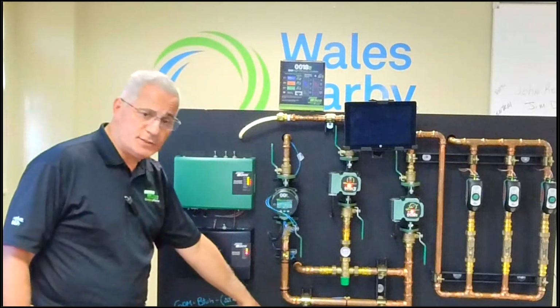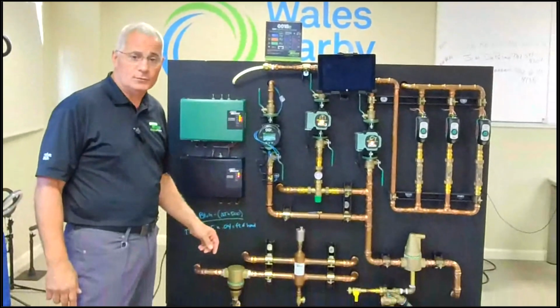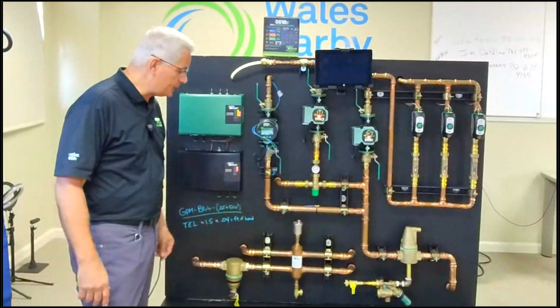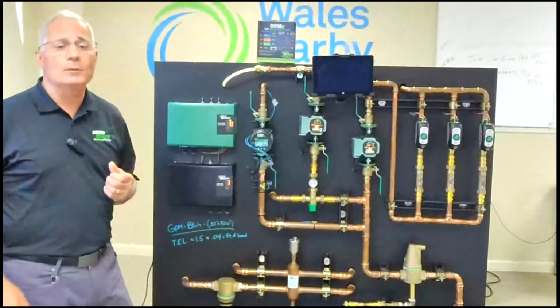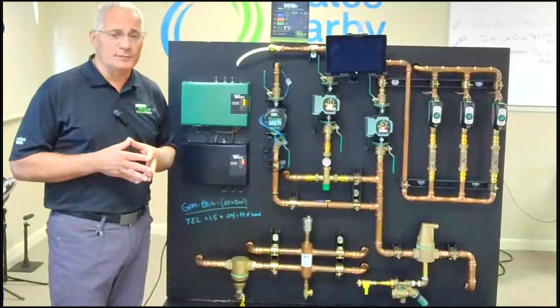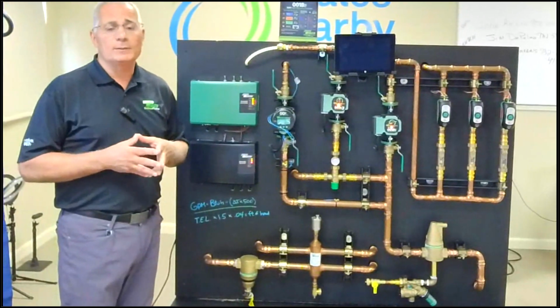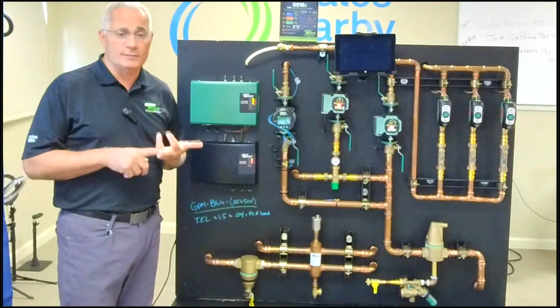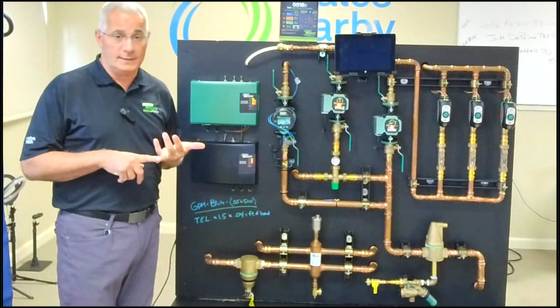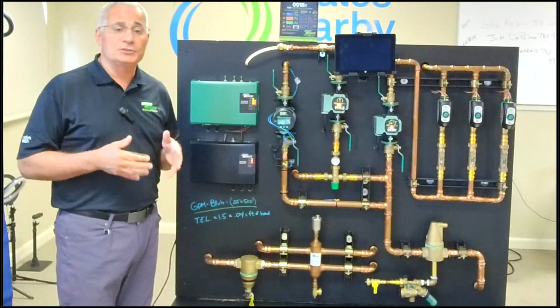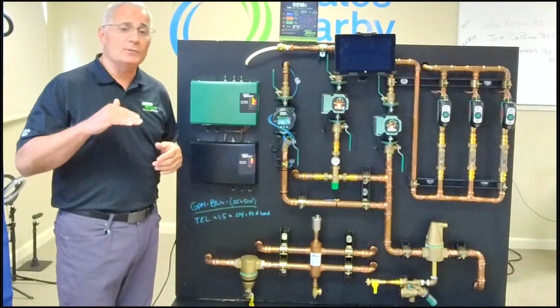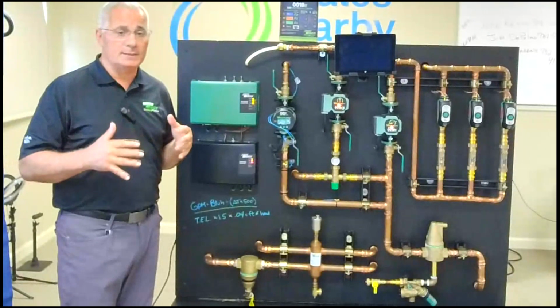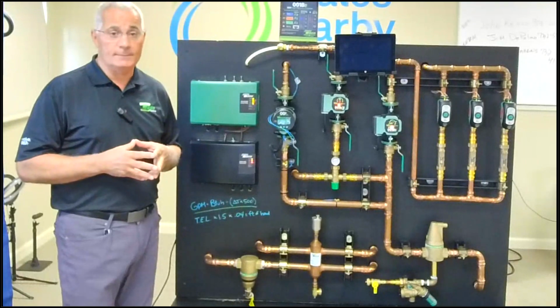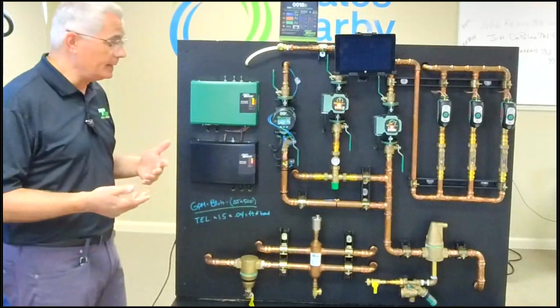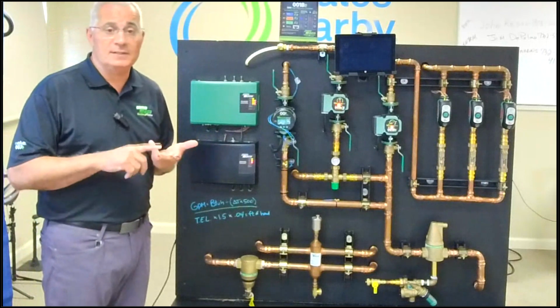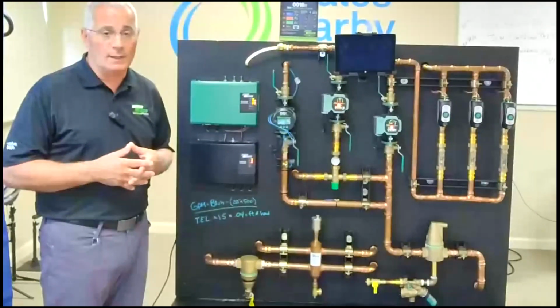Down here, you're going to see this low loss header, because in the world of condensing boilers, we do have two different flow rates. My boiler could be at a 20-degree delta, a 25-degree delta, a 30-degree delta. Every manufacturer will show you in their install guide where you can set that boiler pump based on delta T, what you want to attain. And then out in my system side, I can have 10, 15, 20, 25, whatever delta I want.